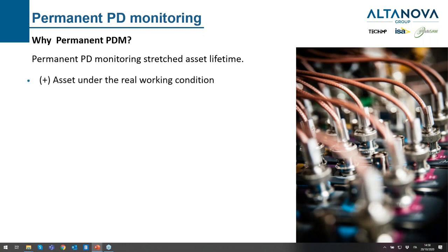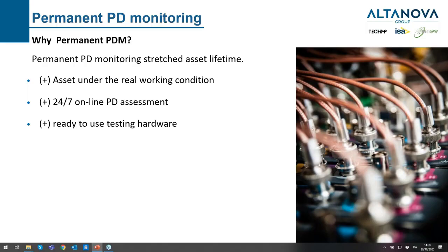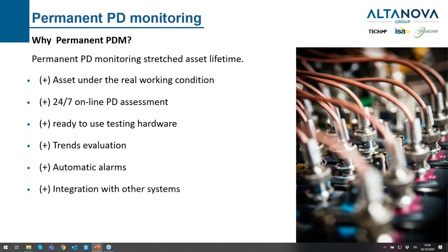Why should we install permanent monitoring? The asset works in real working conditions all the time and we have 24/7 online PD assessment. We also have the testing hardware ready to use if we want to perform a manual spot measurement. Suppose we want to investigate an alarm a little more — we already have everything in place, we just need to connect a laptop. We can have very good trend evaluation and automatic alarms.